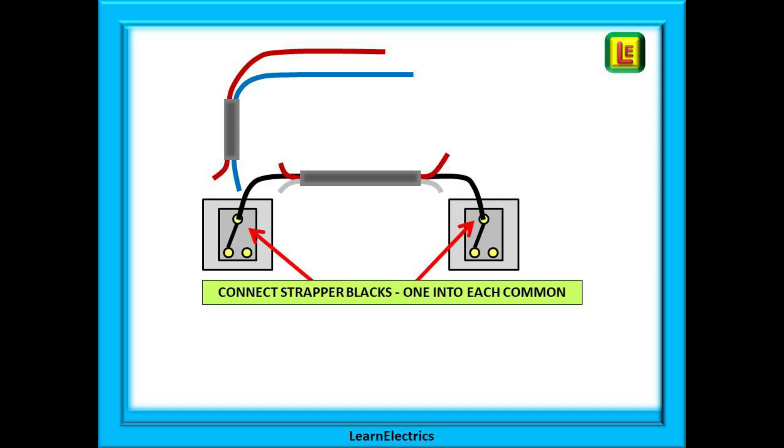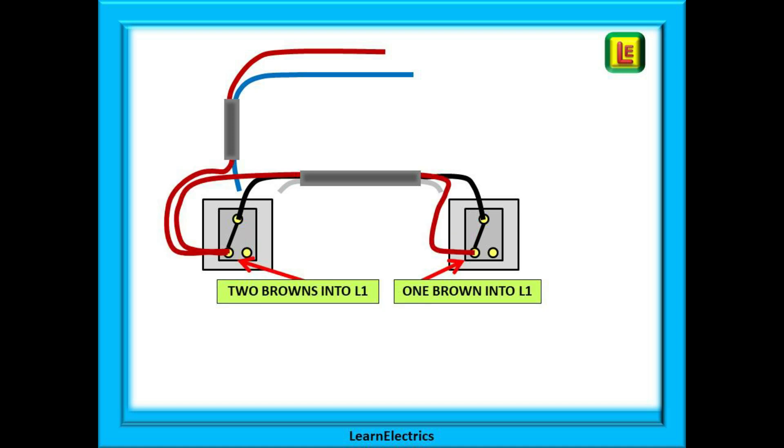Let's begin and start to build the circuit up. This is how I do it. First, connect the black of the strapper to the common terminal of both switches, not forgetting to put some brown sleeving on it. At the first switch you will have two brown wires, one from the twin and earth and the other from the strapper. Put these two browns together into terminal L1. At the second switch you have only one brown; put this into L1.